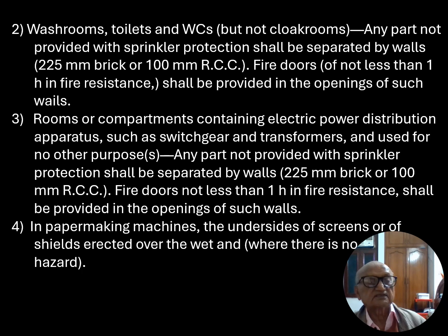Friends, we are discussing the areas of the buildings where the fire water sprinkler need not be provided. The second category is bathrooms, toilets and WC, but not the cloak rooms. Cloak rooms are the rooms provided for keeping your luggage if you are brought into that particular building. Any part not provided with sprinkler protection shall be separated by walls of 225 mm brick or 100 mm RCC. The fire door of not less than 1 hour in fire resistance in such cases.